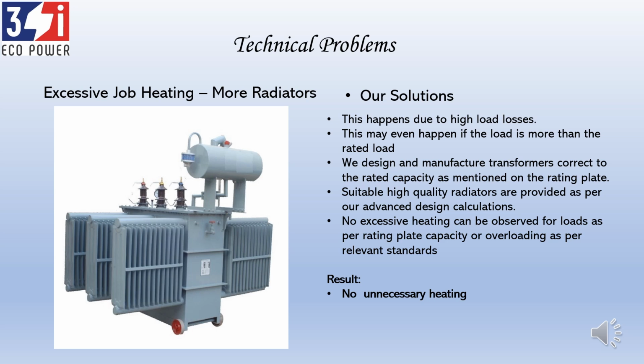A high quality radiator with more fluid per section will dissipate more heat. For the same transformer of the same capacity, if we are giving fewer radiators, it is because of the suitability of the radiators. The radiators we give are more than sufficient to dissipate the heat generated by the transformer, or the losses generated by the transformer. We comply with the losses we guarantee, and the radiators will be as per the design. And the idea that having more radiators means it's a good transformer is incorrect.